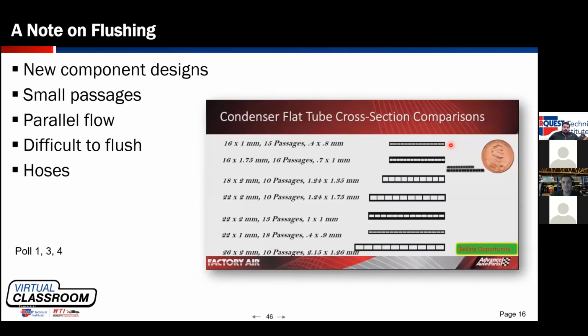So it looks like it's kind of leveled out. Almost everyone got the correct answers on this one. The choices were, what does the machine do? Some choices were nothing. You should add 2 to 4 ounces of refrigerant for every charge. That's definitely not the case. That is not a best practice. The 2 that the machine does is charge compensation, either the machine knowing how much refrigerant is in the machine and how much it needs to add, or hose compensation, meaning that after we're done charging, we're going to take that refrigerant that's in the hoses and pull it into the machine. So almost everyone got those, either one or both of those answers. So next one's number 3, cool.